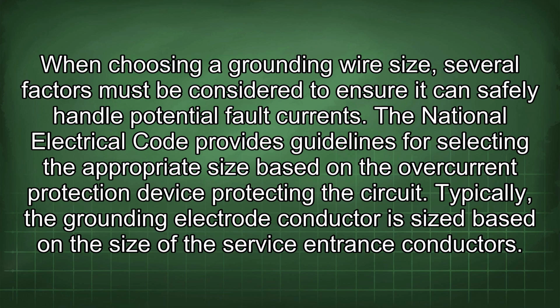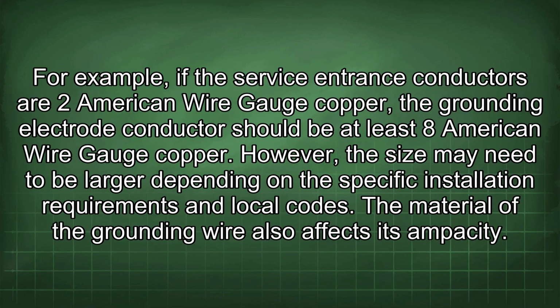When choosing a grounding wire size, several factors must be considered to ensure it can safely handle potential fault currents. The National Electrical Code provides guidelines for selecting the appropriate size based on the overcurrent protection device protecting the circuit. Typically, the grounding electrode conductor is sized based on the size of the service entrance conductors. For example, if the service entrance conductors are 2 American wire gauge copper, the grounding electrode conductor should be at least 8 American wire gauge copper. However, the size may need to be larger depending on the specific installation requirements and local codes.